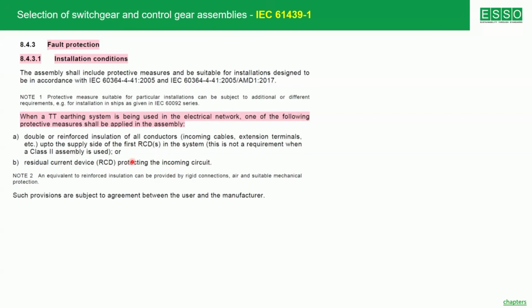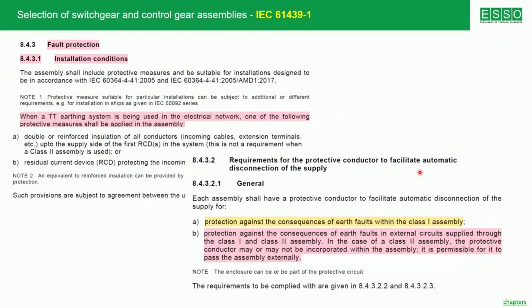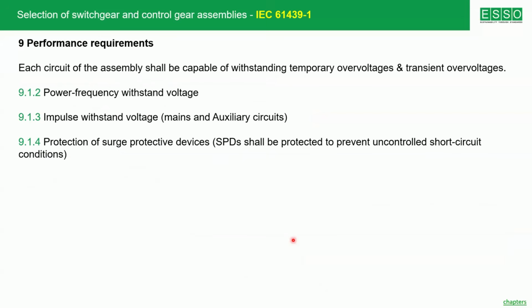This also means if you are going for another system like a TN system, then the arrangement is a little bit different. There is a requirement of protective conductors to facilitate automatic disconnection. The same standard, IEC 61439 Part 1, clause 8.4.3.2.1: each assembly shall have a protective conductor to facilitate automatic disconnection of the supply for protection against the consequence of earth fault within the class 1 assembly, and protection against the consequence of earth fault in external circuits supplied through the class 1, class 2 assembly. That means there should be a provision for automatic disconnection in every assembly for the internal fault as well as all the external faults. Of course, the continuity of the protective conductor is very much necessary. The earthing continuity is very much necessary.